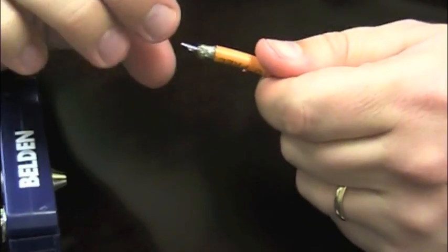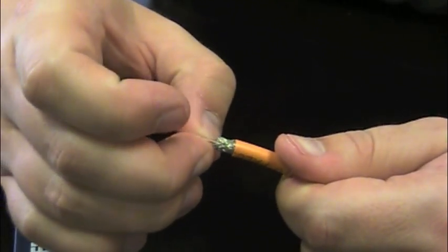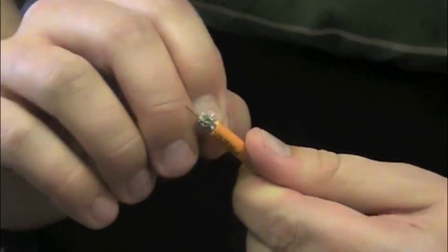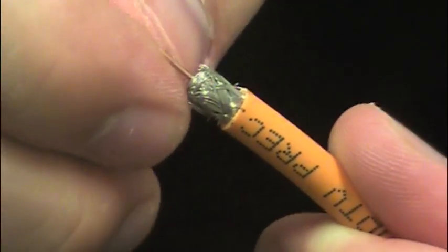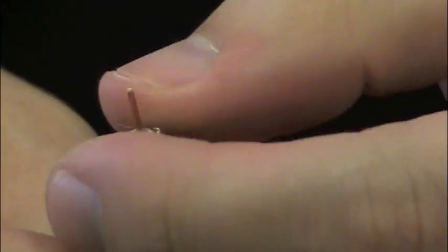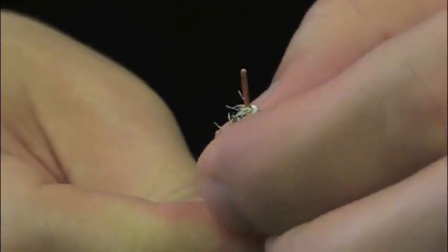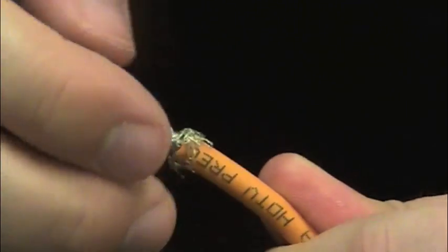Now what you want to make sure is there was some braid shield that was left on here. You want to make sure that nothing is touching the center conductor. So in this case, there's a little bit wrapped around, so you're going to want to go ahead and make sure that all that's pulled off the center conductor, because that'll create a short. And while doing that, you want to make sure you fold the braid back down over the jacket. So we're just going to go ahead and do that. There's really no trick to this. You just kind of pull it with your fingers and get it over the jacket and push it down as much as possible.